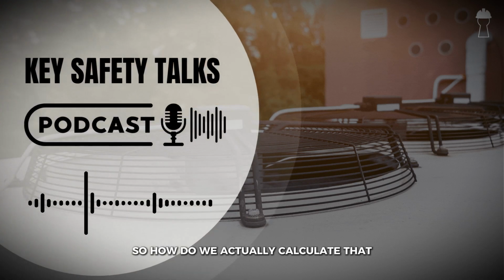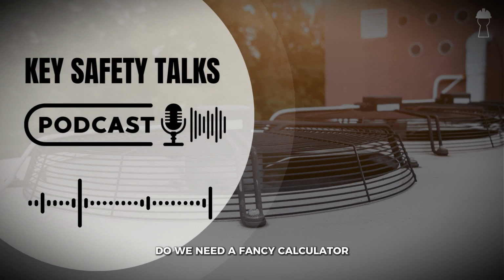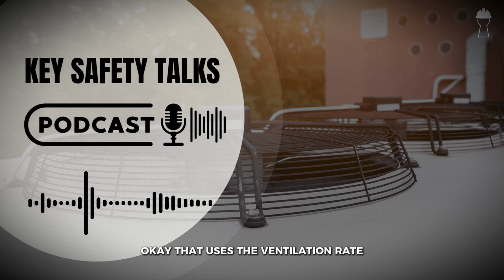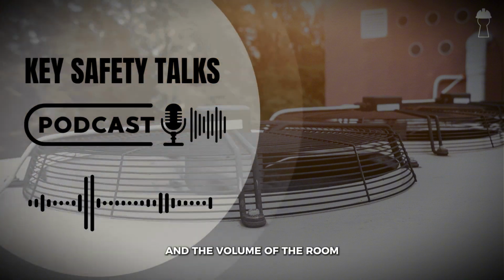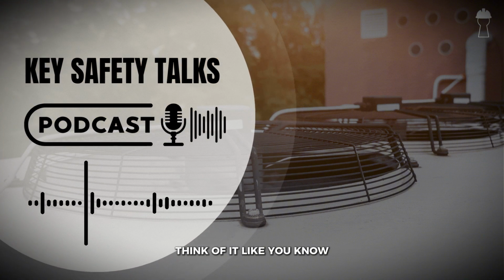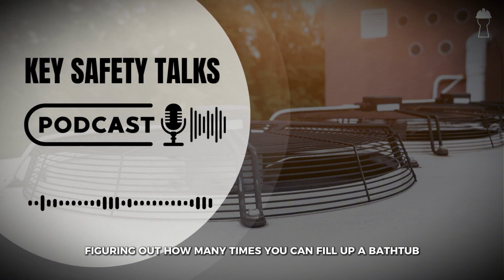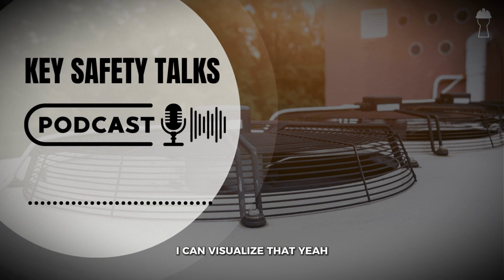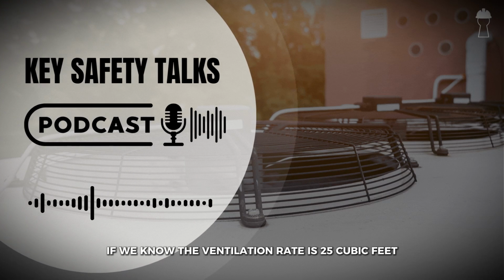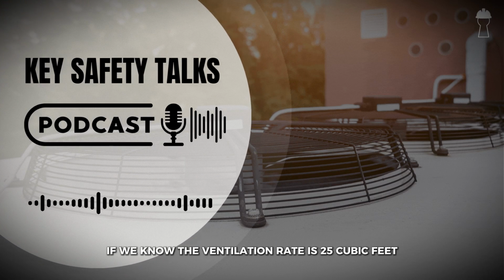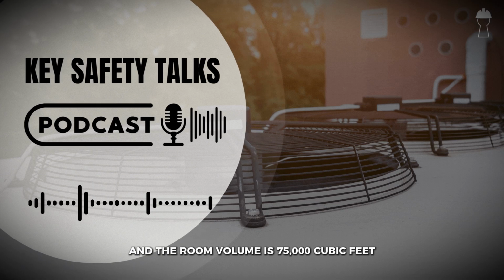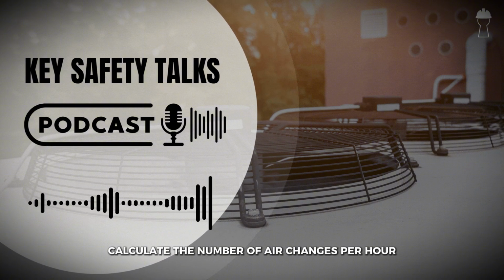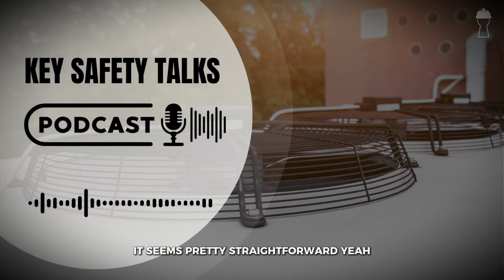So how do we actually calculate that? Do we need a fancy calculator? Nope, not at all. The guide gives us a nice straightforward equation that uses the ventilation rate and the volume of the room. Think of it like figuring out how many times you can fill up a bathtub using a certain size bucket. Okay, I can visualize that. So for example, if we know the ventilation rate is 2,500 cubic feet per minute and the room volume is 75,000 cubic feet, we can easily calculate the number of air changes per hour. It seems pretty straightforward.